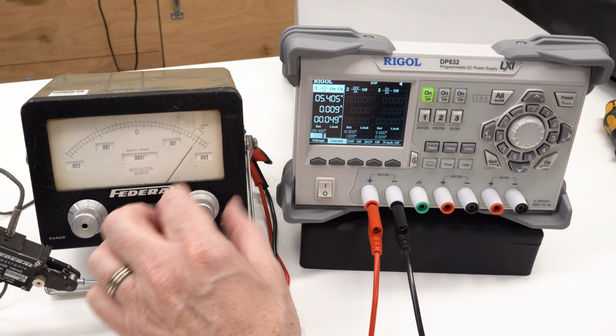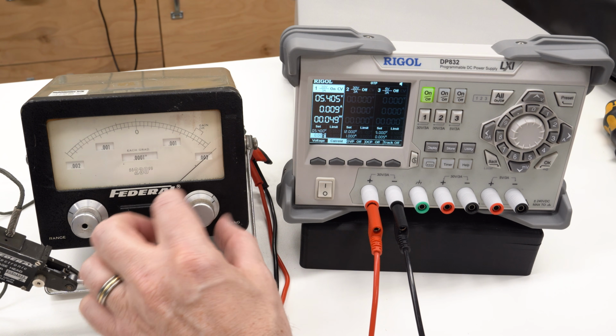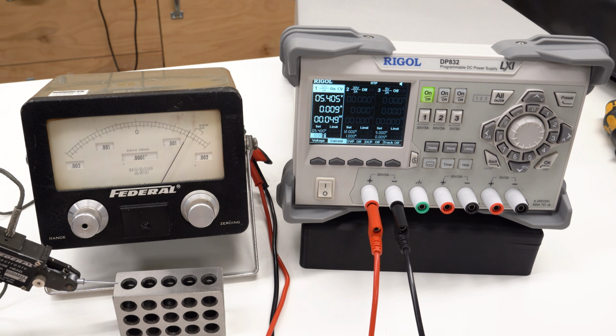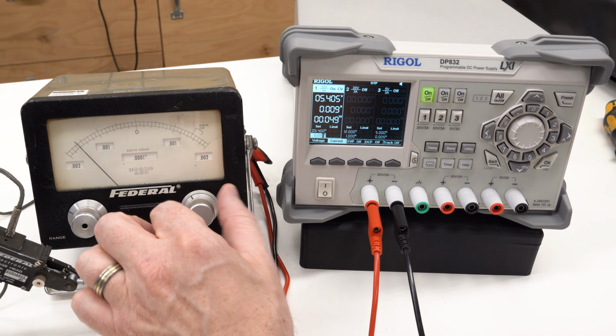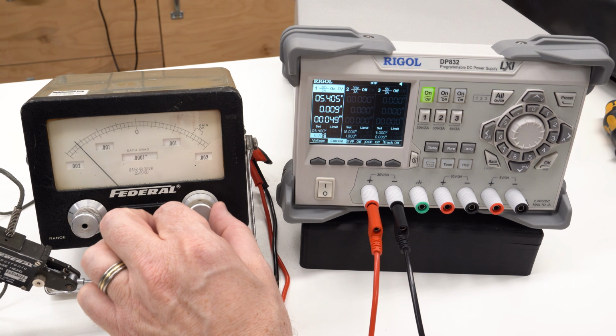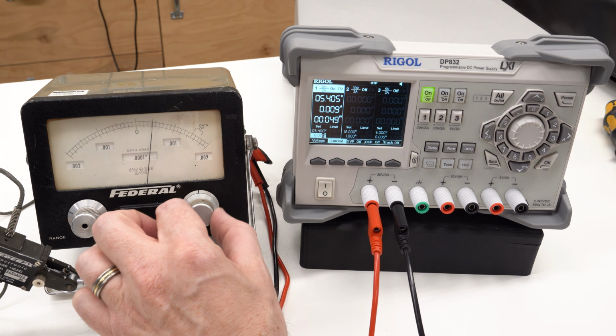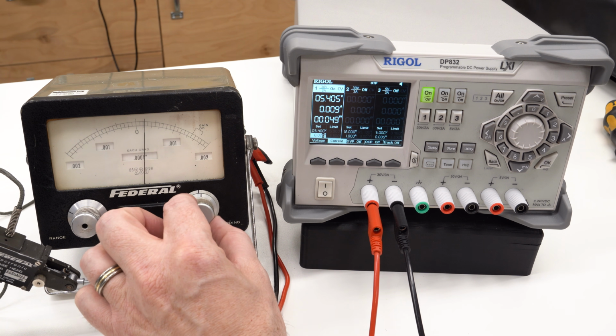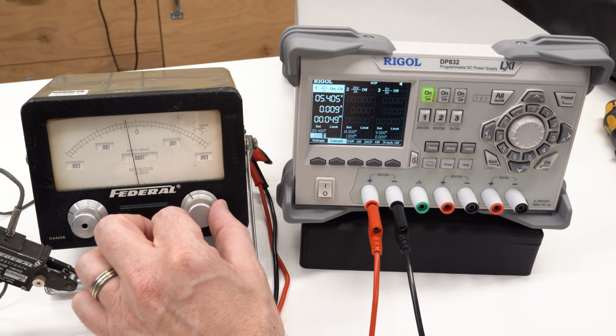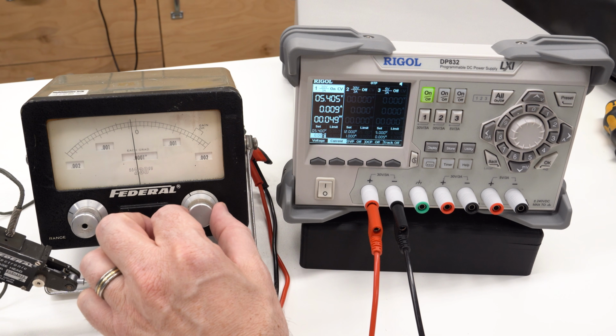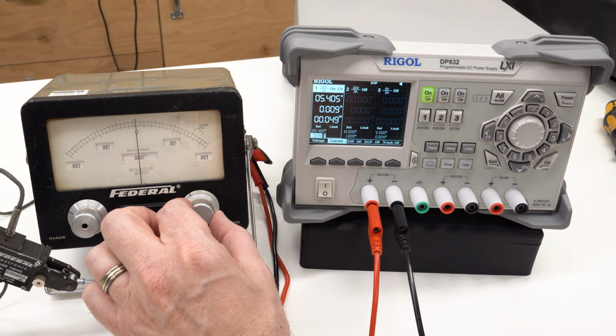And it seems I'm outside of the range of the adjustment here. Let me move this mechanically down so that we can reach 0. Then with the electrical zeroing knob, there's the fine adjust. Then we'll hit the coarse adjust, bring it up, bring it back down a little bit. That was too far. And yeah, we can bring it to 0.